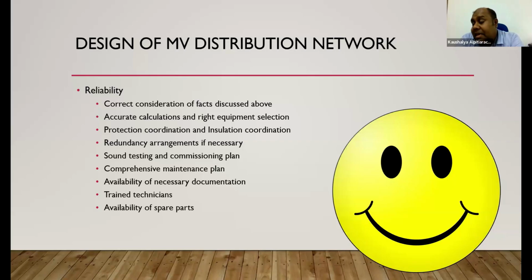Sound testing and commissioning plan and sound installation plan. So whatever is selected to install has to be properly installed with good and acceptable workmanship, and shall be tested before energizing or before commercial use. So for that, you should have a sound installation as well as a testing and commissioning plan.